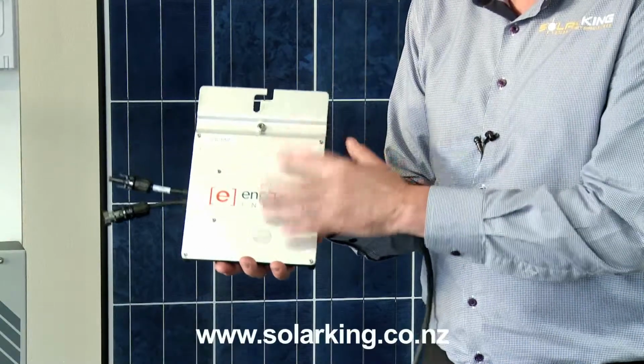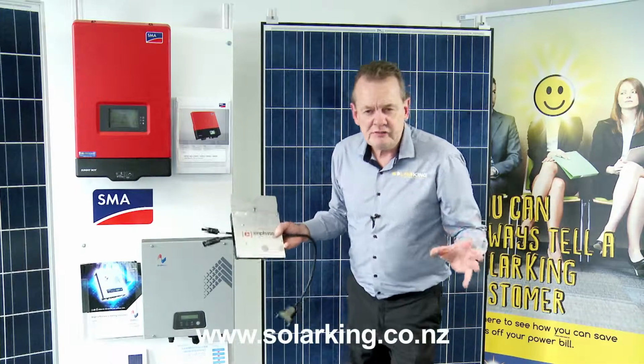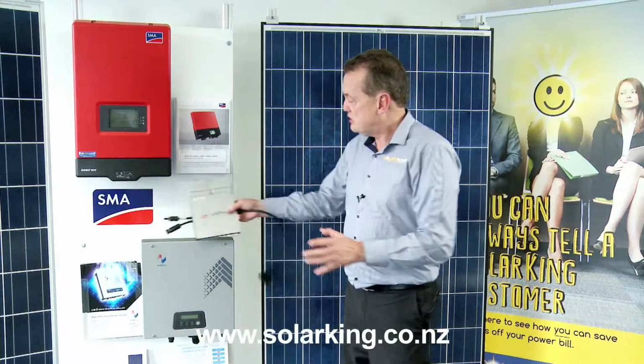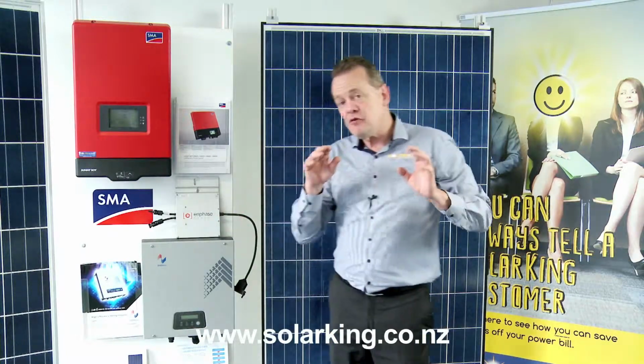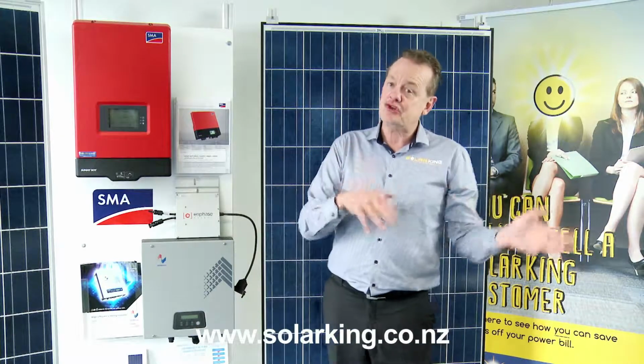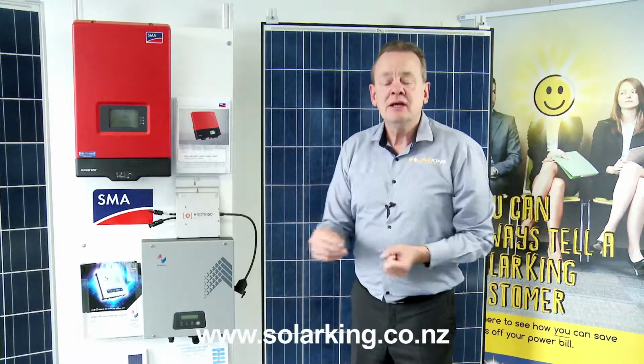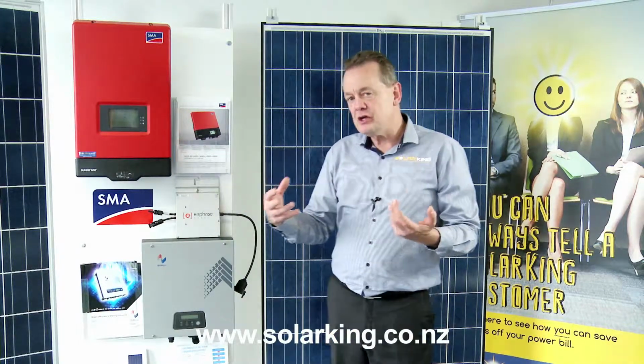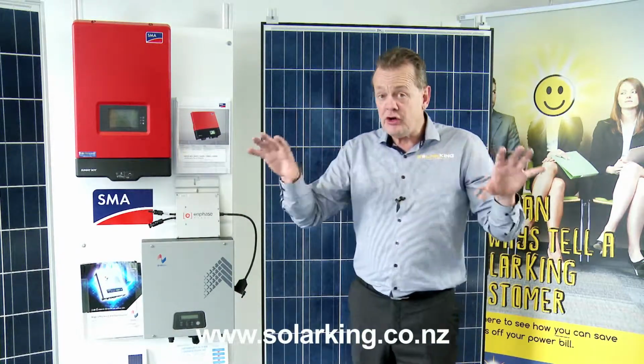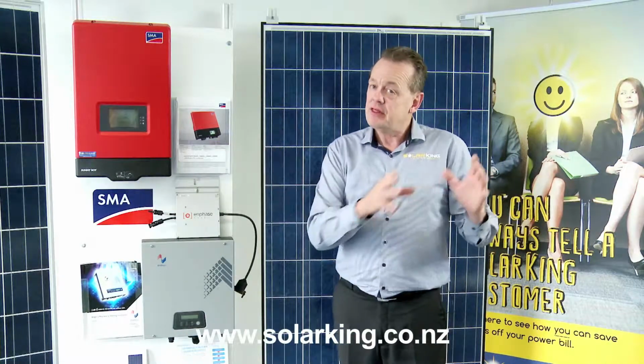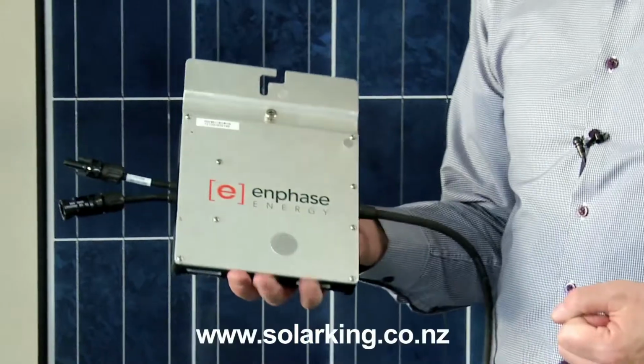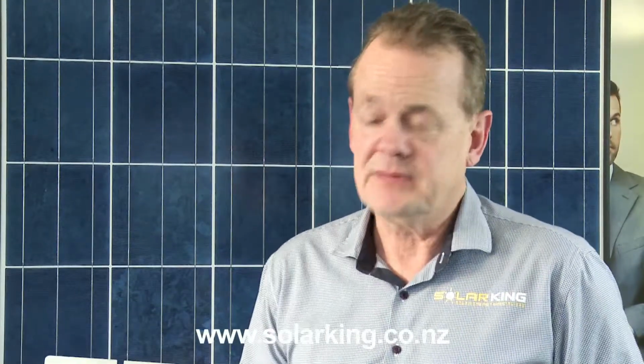One of the main uses for microinverters, without getting into the science of it: if you have a massive array of panels and you're using a string inverter, and if one panel at the end gets shaded by a tree or a lamppost or a chimney, what happens? The electronics of your string inverter drop the performance of that entire array of panels to match the lowest performing panel. One inverter under every panel, and what happens is that that panel then becomes a standalone energy producer, what we call open architecture. So if one panel gets shaded, you only lose the production of that one panel, not the whole system.